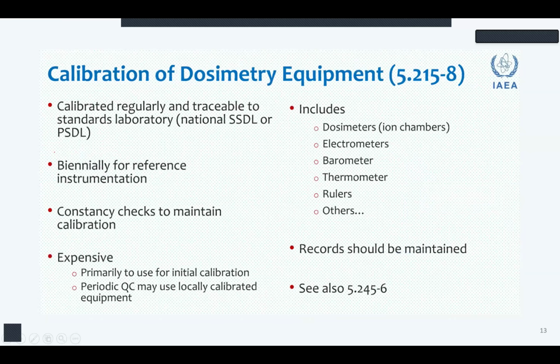In terms of dosimetry equipment themselves, of course, they have to be calibrated if they're used for calibration themselves, and they should be traceable to standard laboratories like the national SSDLs or the primary standard dosimetry laboratories. Once every 2 years, biennially, this should be done for this kind of equipment. But importantly, in the interim, between those 2 years, we should have regular periodic checks at our own center using check sources, for example, strontium sources. The whole procedure is fairly expensive, but it's worthwhile and includes a variety of equipment, not just the dosimeter.